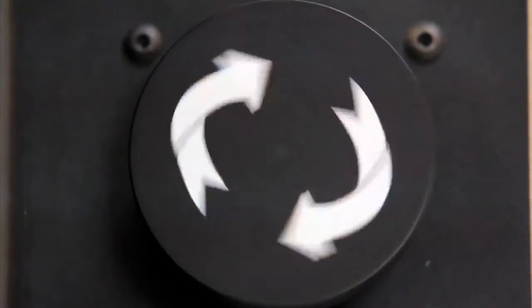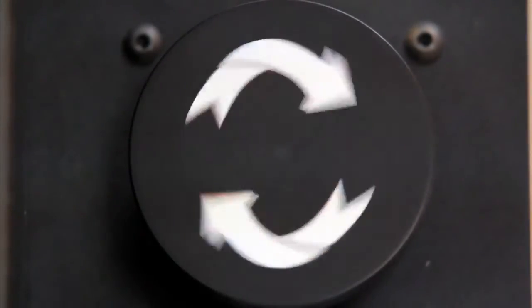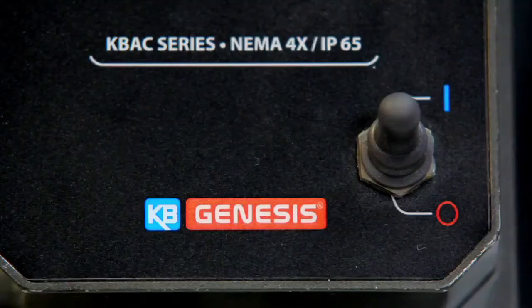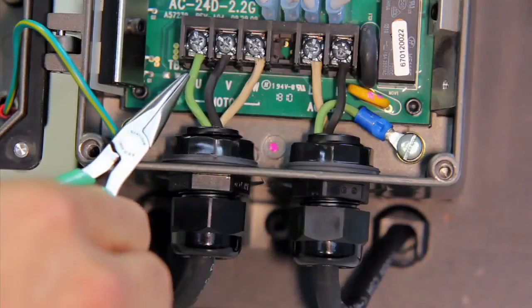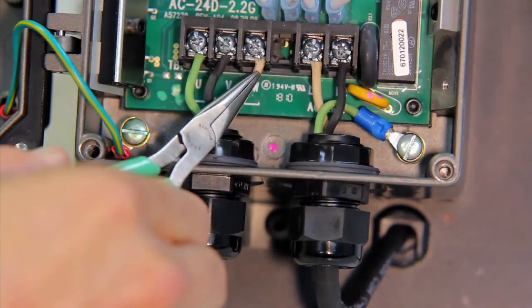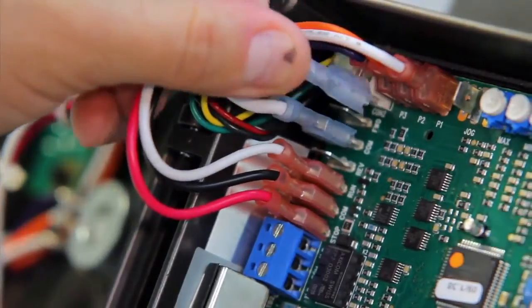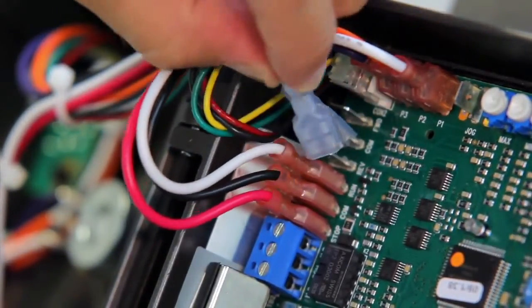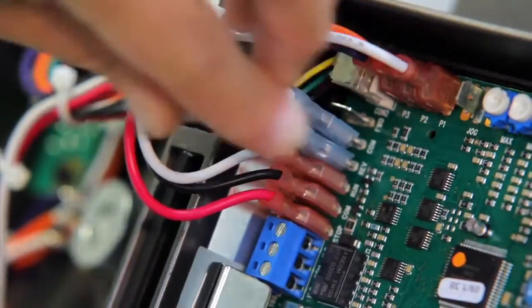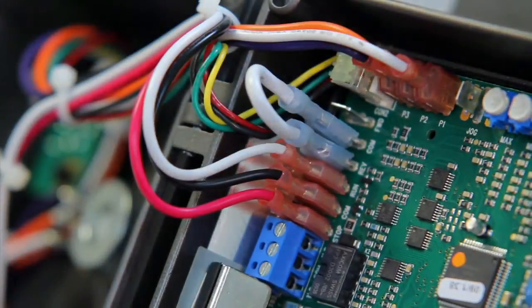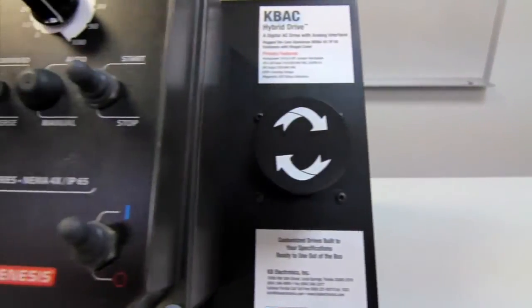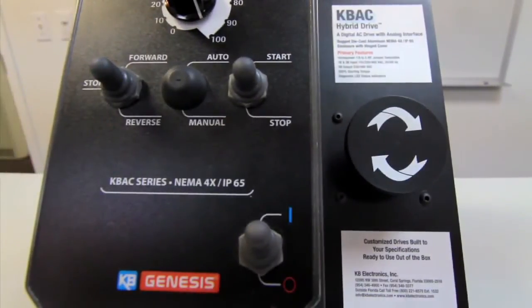Check the motor shaft and make sure it is rotating in the correct direction. If it is not, power off the drive and reverse any two of the U, V, or W lines. You can also change the rotational direction by moving the jumper from the forward and COM position to the reverse and COM position. This feature is also available on drives that have the optional forward stop reverse switch installed. Just reverse the forward and reverse leads.